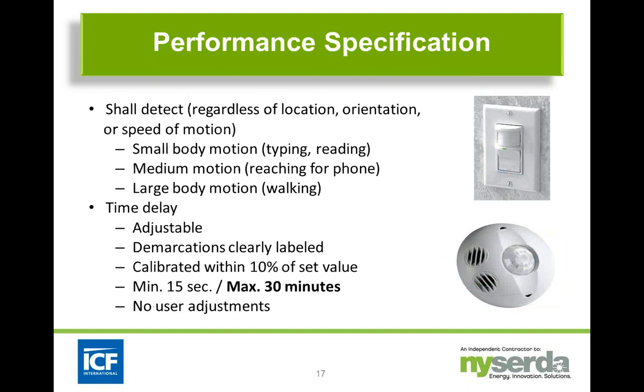Another group of performance specifications, you want to talk about what it can detect regardless of the location or orientation. So if you have a device that needs to see small body motion, you want to put that into your specification. So like typing or reading, that's good for a passive infrared wall-mounted switch. It will see small body motion, or medium body motion, like reaching for the phone. You want to make sure you're specifying the motion that's appropriate for your particular space.